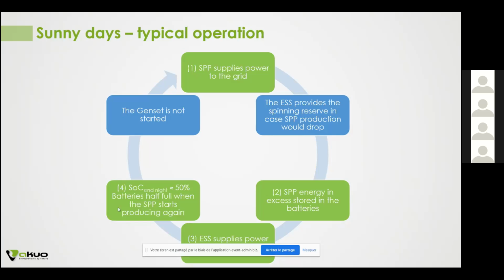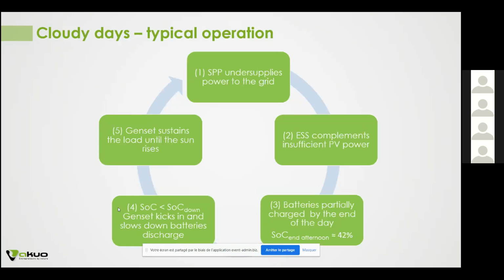The solar power plant produces electricity during the day. The excess is stored in the ESS, the storage technology, which provides the balance of missing power to match demand at all times. By nightfall, the ESS takes over and fulfills 100% of the load. Throughout the night, because the system is oversized for year one, eventually as we go over the years and the system is less oversized, it becomes similar to a cloudy day today, where the genset kicks in towards the end of the night to take over demand matching until the early hours and sunrise, when the solar and the ESS take over again and the genset switches off.